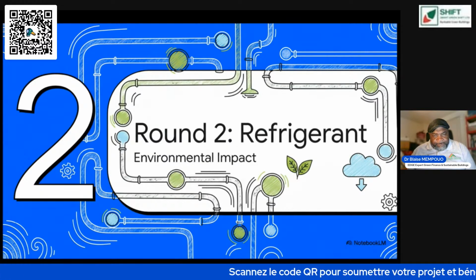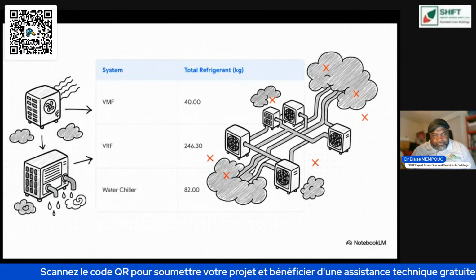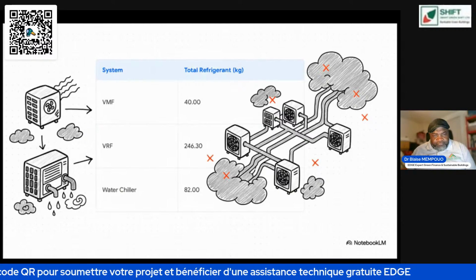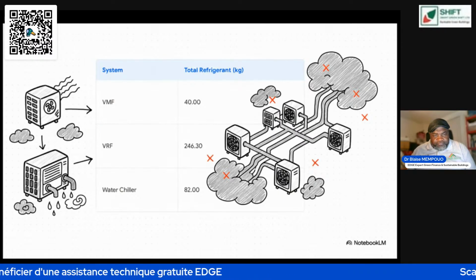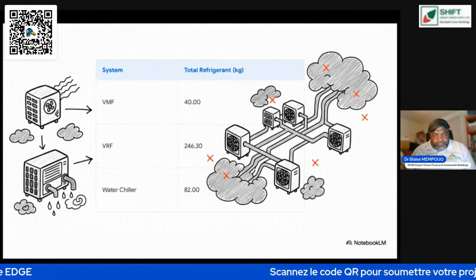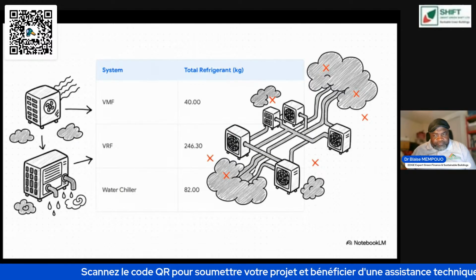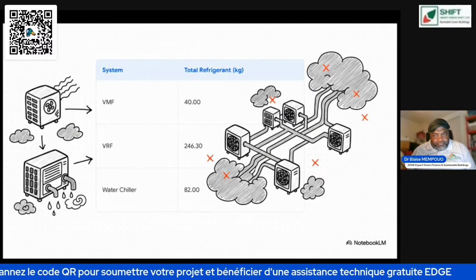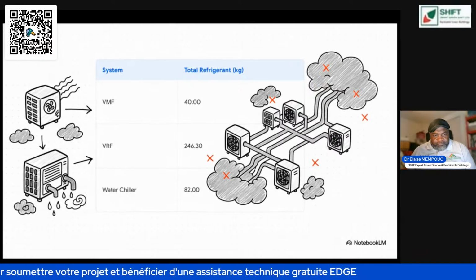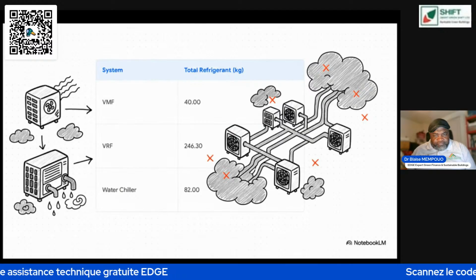So just how much refrigerant does each system need to operate? The results almost perfectly mirror what we saw with power consumption. The VMF system is incredibly lean, needing only 40 kilograms of refrigerant. The water chiller doubles that to 82. And the VRF system needs a staggering 246 kilograms, over 6 times the amount of the VMF. A big reason for that is VRF systems have copper piping full of refrigerant running throughout the entire building, which can have big implications if there's a leak or when dealing with environmental laws.